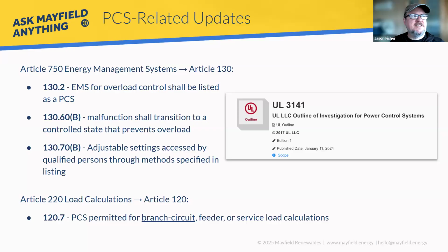The other one - and you're starting to see this, some companies were ahead of the times because they were actively engaged - is that you can have a single inverter. Gone are the days where you had one inverter, same size, shape and weight, but with four different nameplates on it to allow four different connection options. Now with PCS built into it, the PCS just controls the output of the inverter, allowing you to tune the maximum continuous output to a rating that matches your design requirements and interconnection requirements, etc.